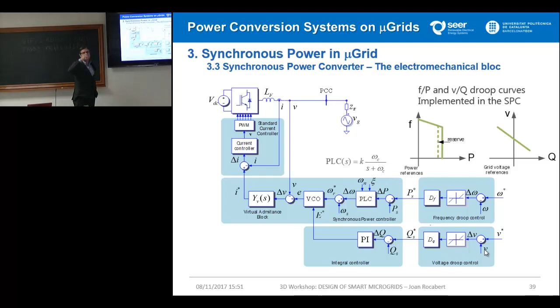So this E is imposed by a droop of the required frequency or the required voltage amplitude, or this block is optional - this E is imposed by some P and some Q imposed by an external controller, like the microgrid controller, the central microgrid controller. You can go to the level that you want.